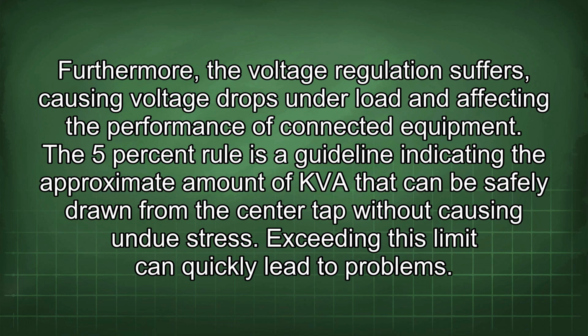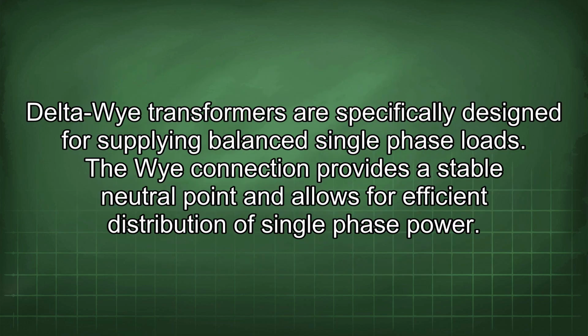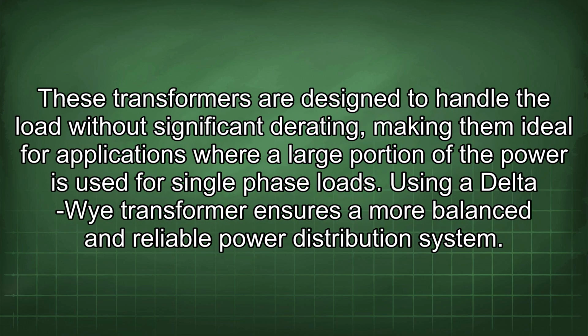The 5% rule is a guideline indicating the approximate amount of kVA that can be safely drawn from the center tap without causing undue stress. Exceeding this limit can quickly lead to problems. Delta-Wye transformers are specifically designed for supplying balanced single-phase loads. The Y connection provides a stable neutral point and allows for efficient distribution of single-phase power. These transformers are designed to handle the load without significant derating, making them ideal for applications where a large portion of the power is used for single-phase loads. Using a Delta-Wye transformer ensures a more balanced and reliable power distribution system.